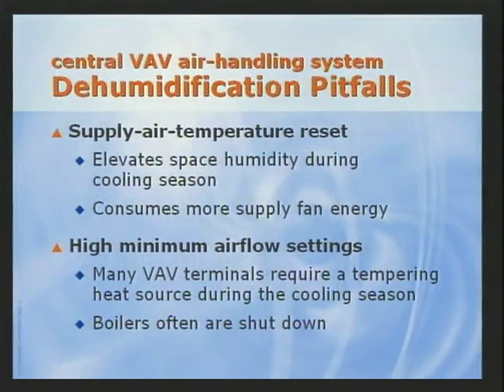Eventually, the sensible cooling load in the space becomes small enough that the required supply airflow is less than this minimum setting. If the air is still delivered to the classroom without being tempered, the space will overcool and relative humidity will increase. The result is a classroom that feels cold and damp. Following are some ways to improve the dehumidification performance of a VAV system.